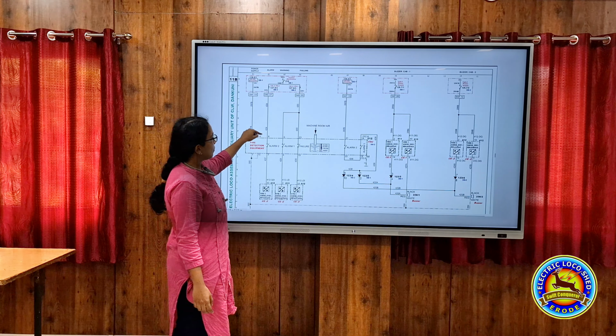This is the circuit diagram for VCU. This is the fire detection equipment, and this is the sub D pin. As I said, 25 sub D pins are there, and across 1 and 4, positive 24 volt is coming from the DC-DC converter, and this is the earth, 2 and 15. And for 8 and 7 across, it is alarm 2, and 5 and 4 pin, it is alarm 1, and 23 and 10, it is failure. And accordingly, this message will be given to the VCU.